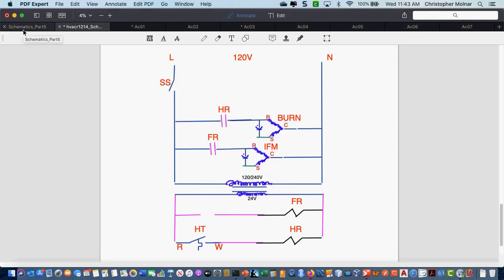Okay, what type of thermostat am I going to use? Heating? Okay, think about what I need it to do. Is it going to close on a temperature rise, or is it going to open on a temperature rise? This is inside the furnace, so I need to blow warm air around the room.